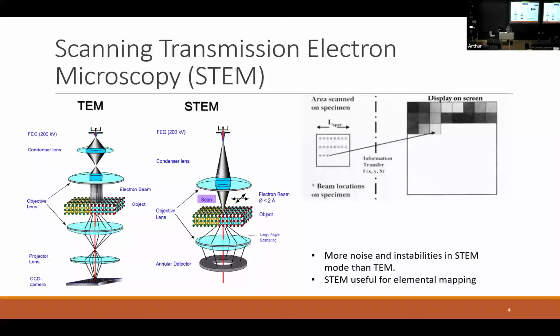In an SEM, if you're familiar with it, you have the beam focused to one spot and you measure the detector output. Then you move it to the next spot, measure the detector output, and build up a raster pattern so that you can gradually build up your image that way. That's what we're going to do in a STEM as well. We take the TEM probe, make it as tiny as we can, focus it on one spot, measure our signal, then move over to the next spot, and then the next. And because we're at these higher energies and have more complicated lens designs, we're able to beat the resolution of a standard SEM by an order of magnitude at least.